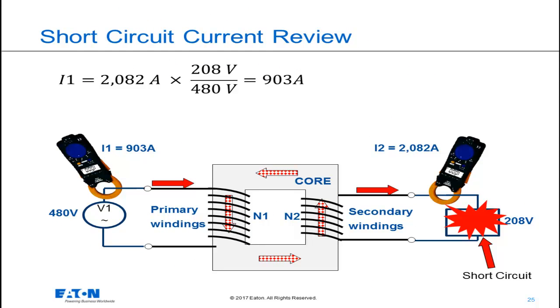This is a different way of looking at the exact same calculation we just made. During this faulted condition, if I place a current meter in the secondary and primary conductors of this transformer, the ammeter on the secondary would read 2082 amps, the current being delivered to the short circuit. The ammeter on the primary would read 903 amps, which is calculated in the equation at the top of this slide.